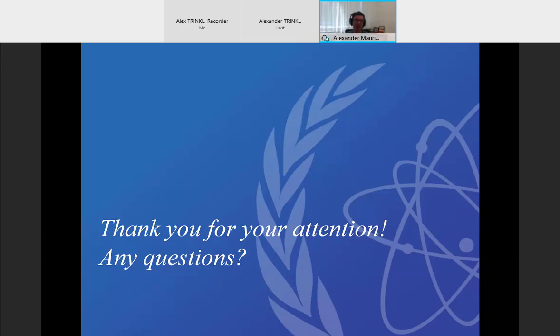It's a little bit of insider information from our lab. We don't have background variation so much during the week. So what we do is we do long background measurements twice per year, but then every month we follow it up with a background check. So we do a short background quality control just to make sure that the general background hasn't gone up or down. So in the end, the background monitoring frequency is every month.